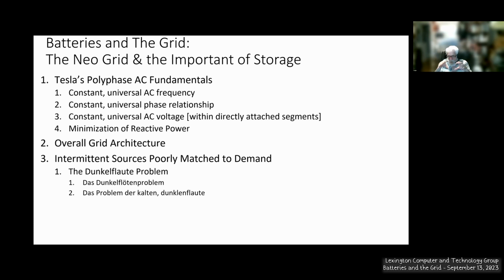The problem comes not from capacitors in the circuit, because there aren't that many naturally occurring capacitors, but from inductors. Anytime you have a motor, you have an inductor. So if you have big industrial facilities, you might have the voltage and current shifted from being in phase to being out of phase by a considerable amount. This causes currents to flow back and forth on the wires that aren't doing any work, but they're heating the wires up, dissipating real energy in the process of meeting the criteria for the reactive elements.